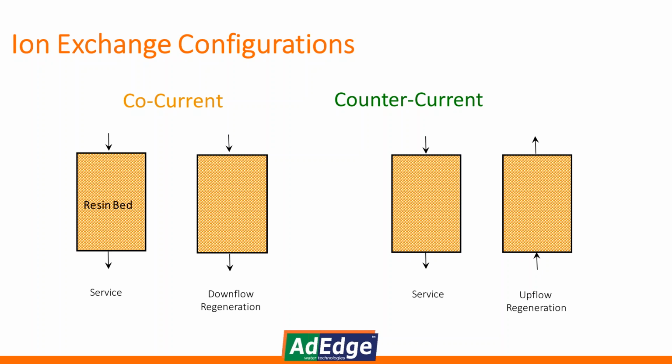climb at the end. So you do have some more variability when you're doing blending with an ion exchange system, because typically you will blend a portion of that raw water around it, and bring it back to a target range of maybe 7 milligrams per liter of nitrogen, which would be 70% of the MCL.